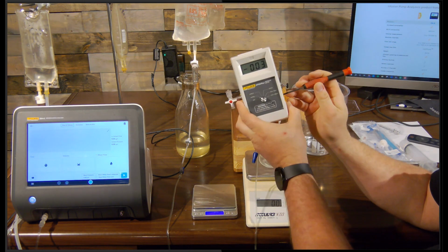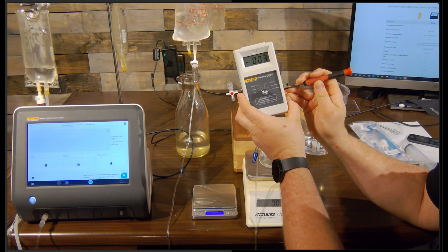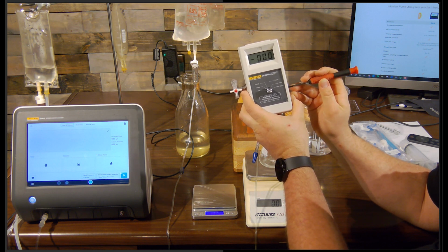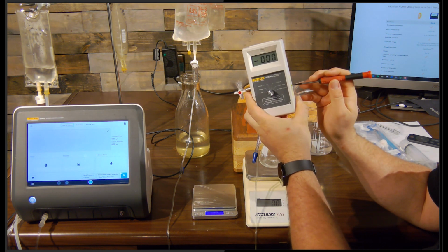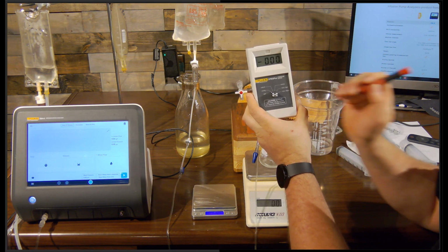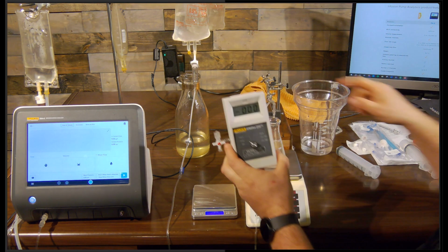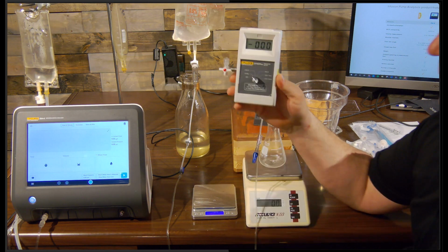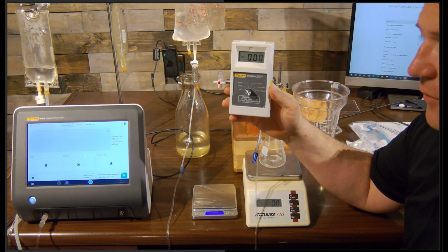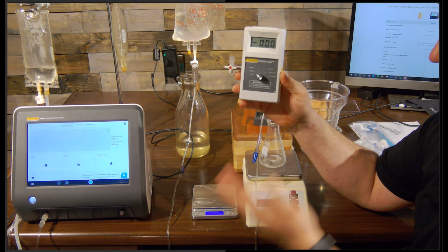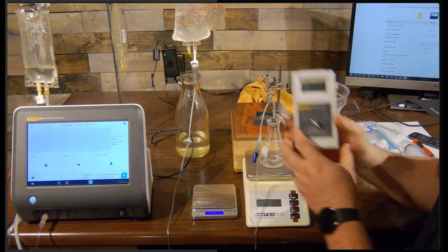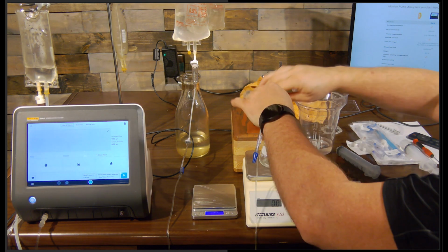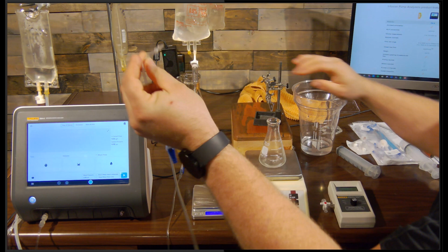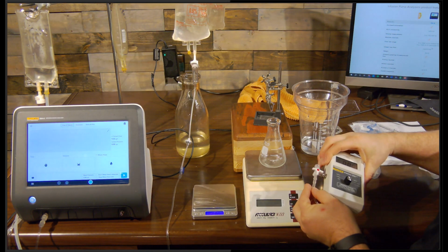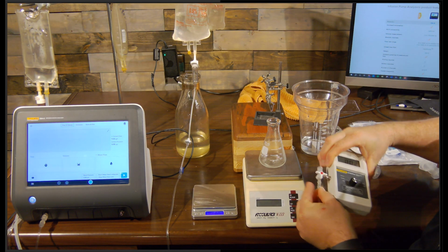Put me too far. There we go, 0.0. You have to make sure that your pressure meter is zeroed out. And again, you need to make sure that your pressure meter has enough resolution by your OEM's manual. So then, I'm done with my flow test. I take my pressure, I take my tubing off here, connect it to my pressure meter, like so.